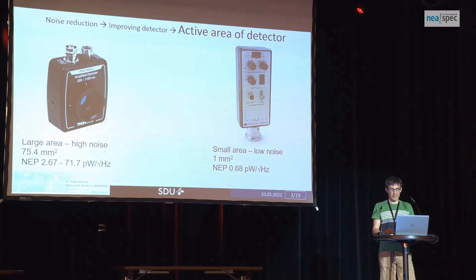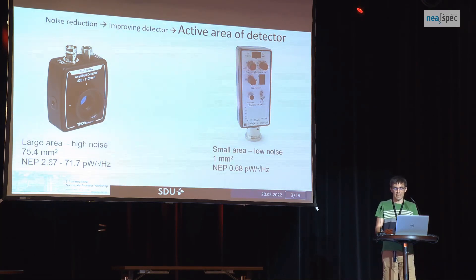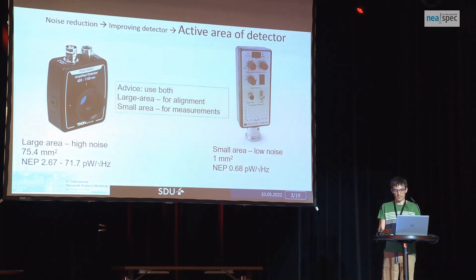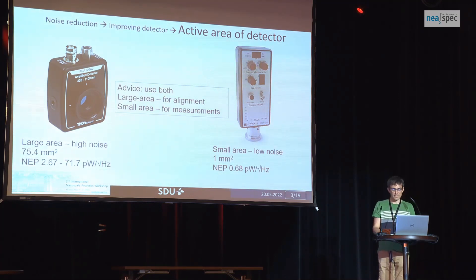So which one to buy? Detectors differ by the area of detection. There are large area detectors, but they have large noise. And small area detectors, which have small noise. My advice is, instead of choosing one detector, use both: use a large area detector for alignment and a small area detector for measurements. The noise difference is actually substantial — by a factor of 5 to 10. You can really reduce the noise from the detector this way.